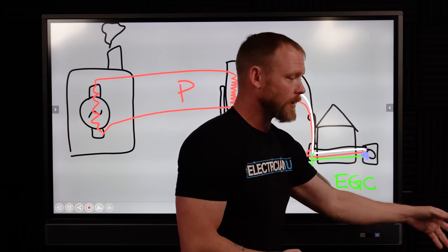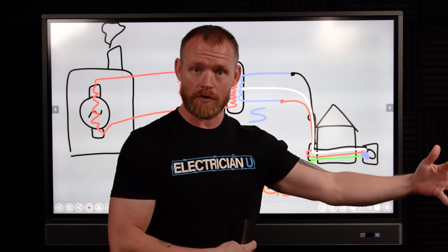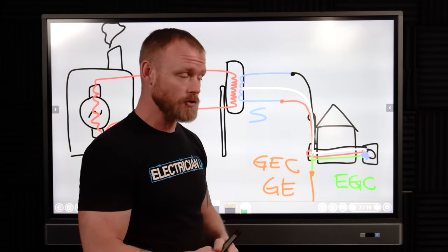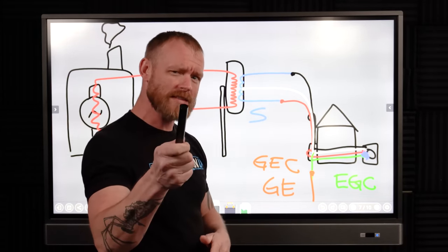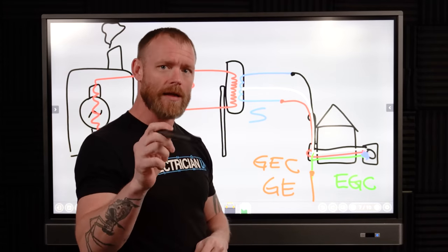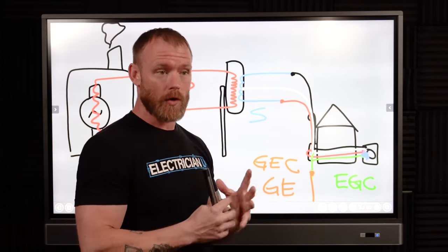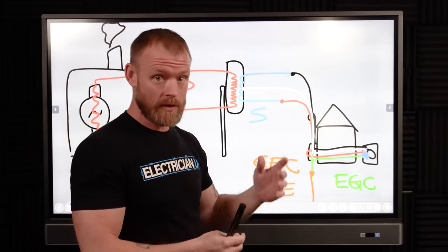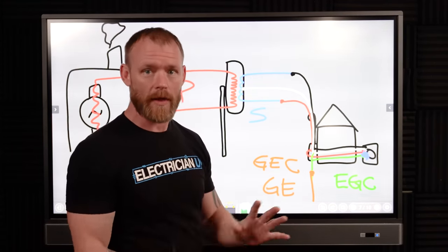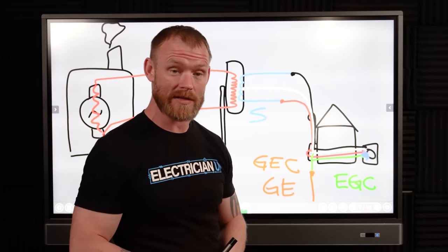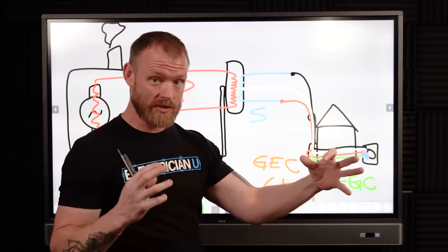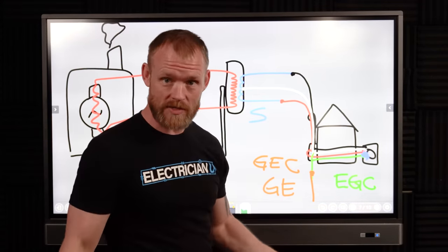The equipment grounding conductor — EGC — is a different thing. It goes out to equipment and has a different function. The grounding electrode establishes conductivity with earth for line surges, lightning, or anything that might happen — maintaining similar potential throughout the system. The EGC provides a fault path; if there's a fault on a piece of equipment, it can actually clear the fault and make a breaker trip. I'll have more videos specifically on grounding and bonding — it's a very complex topic.